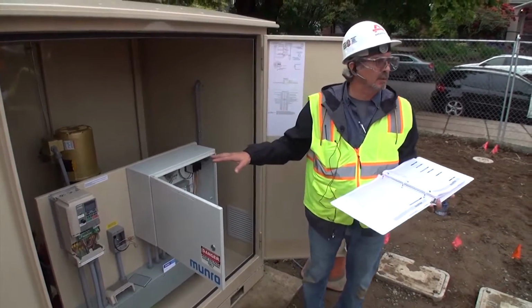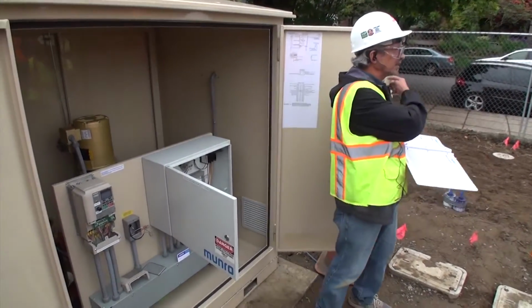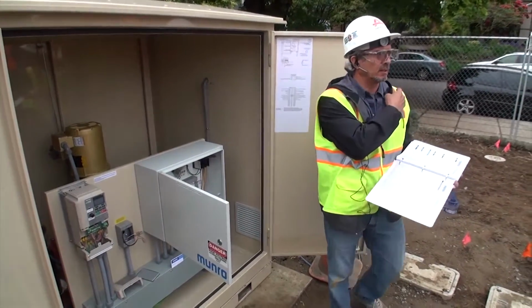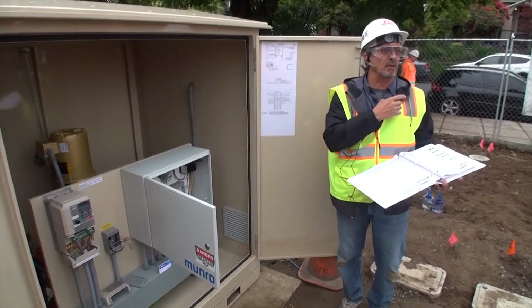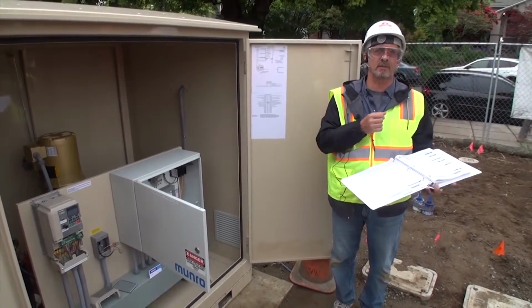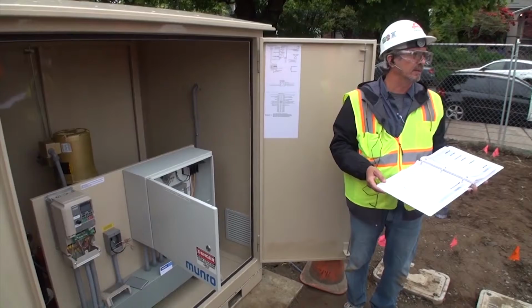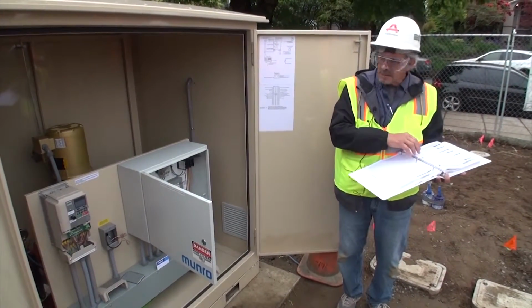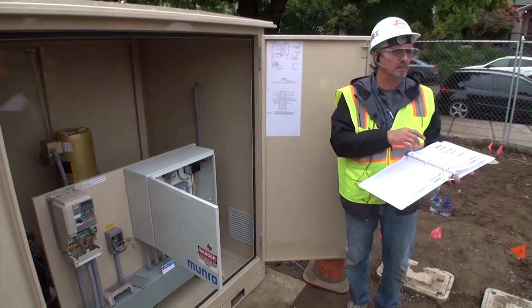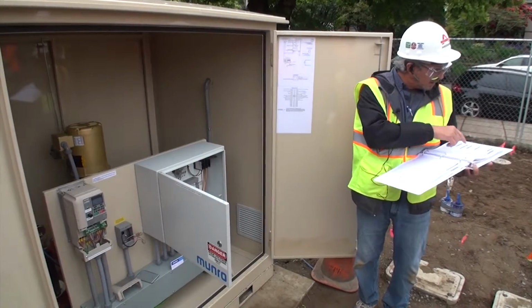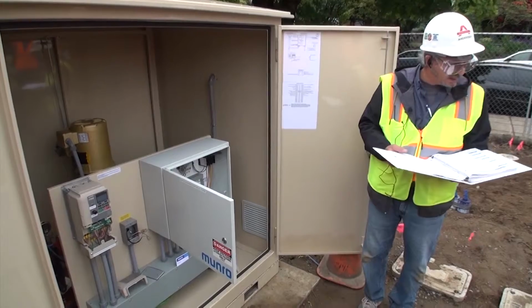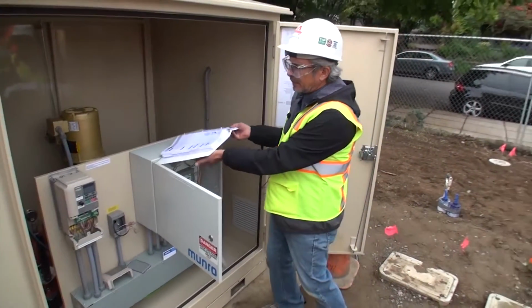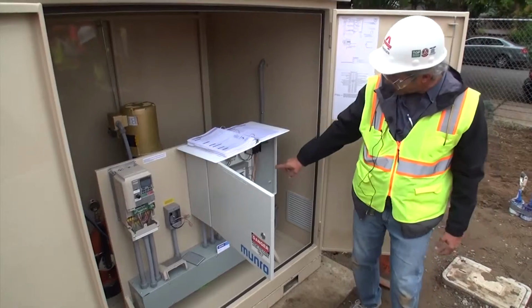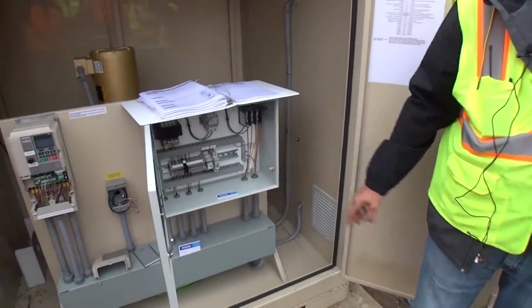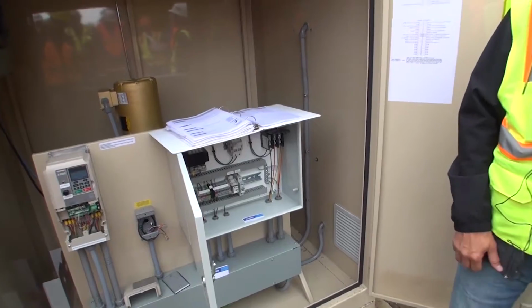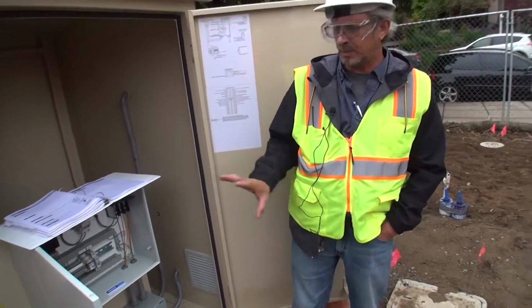Anytime you're doing any kind of work with electrical, you want to make sure that you flip the disconnect off. Don't get yourself electrocuted. A lot of places are going to require you to put a lockout tagout on there. What that does is prevent somebody else from walking in and flipping it on when you're in there. This station is 480, so be careful. So when you're in here though, after you've made sure there's no power, you check it with a voltmeter, you make sure there's no power here. As long as there's no power here, in this case, there's not going to be any power anyplace else. There is only one voltage source in this particular station.